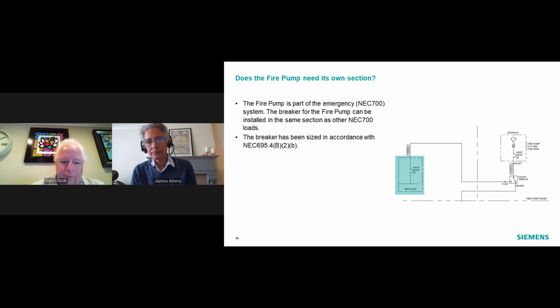So does the fire pump need its own section? And it doesn't. The fire pump is kind of lucky. It can reside in two different sections. It can reside in the, excuse me, I'm thinking of elevators, I apologize. The fire pump is explicitly stated in NEC 700, right in the code, as an emergency load. So it does not need its own section. It can be there in the same section as the emergency loads. In this case, the breaker has been sized in accordance with NEC 695.4B 2B.